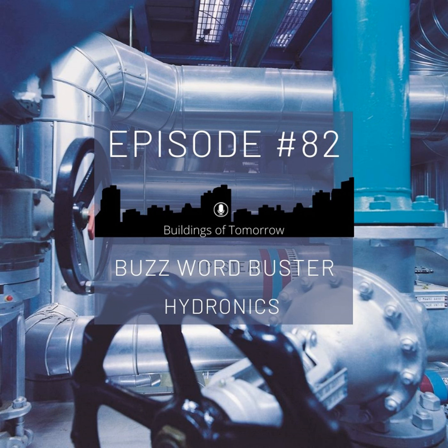And the first one you mentioned was a delta P constant at the endpoint. So picking the part of the system which is the furthest away, as an example, from the pump, and making sure that the delta P provided at that point is up to the minimum or the expected requirements, which gives us some transparency at the end point. And we just assume that if the people furthest away are getting enough water, then everyone else is getting enough water as well.